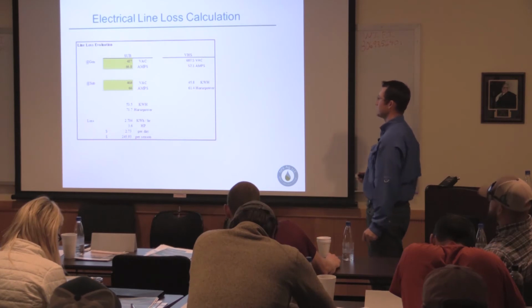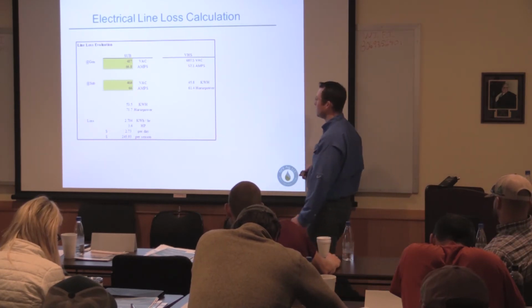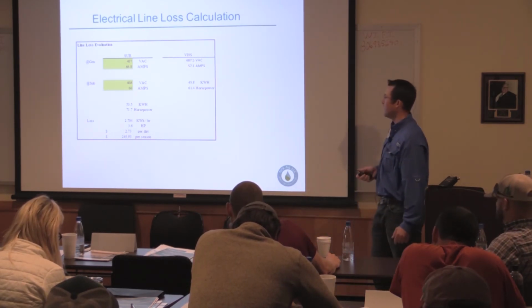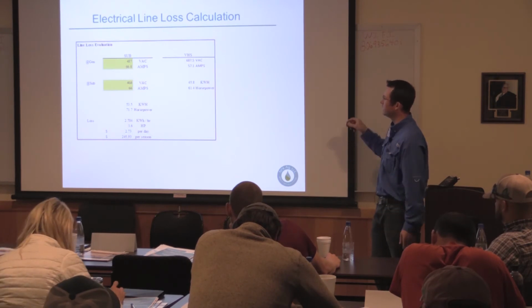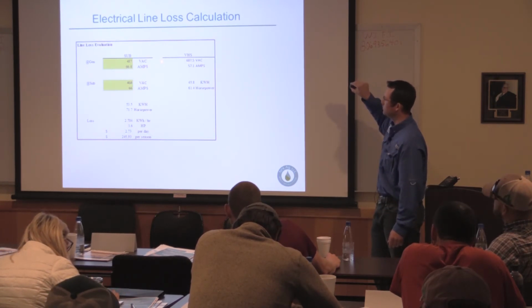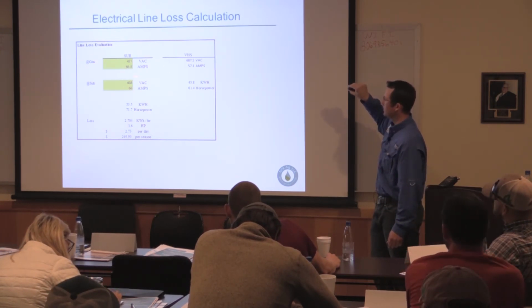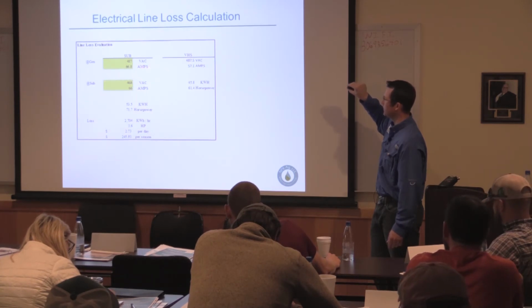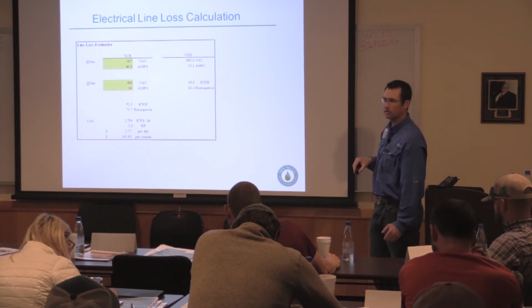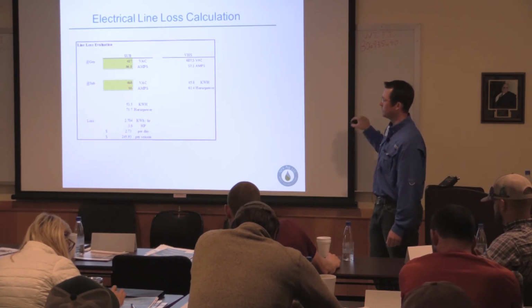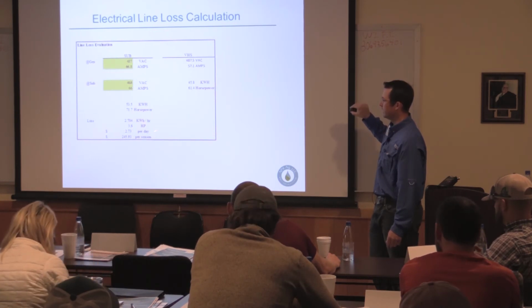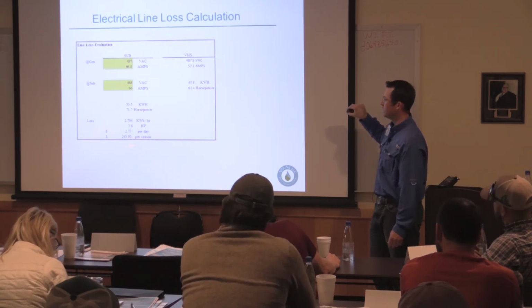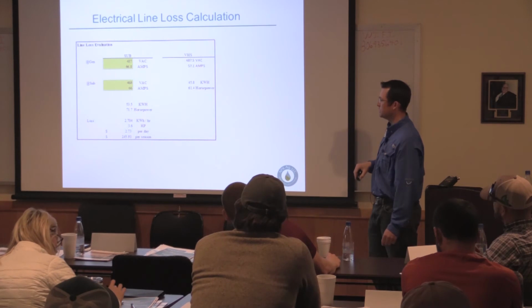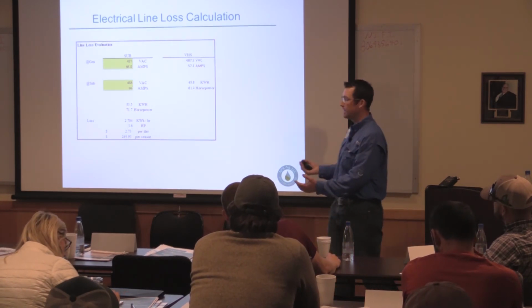Line loss calculations are important. This is again an actual one after the fact, but you can do this theoretically beforehand. What we did here is we took volts and amps at the submersible, and at the genset. And as you work through it, we come out to find that we had a loss of 2.7 kilowatts in the process. Okay, and when you go through the math, again, it's not much.